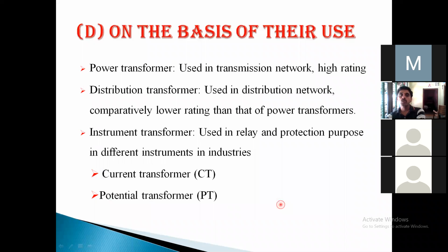So on the basis of use: power transformer, distribution transformer, instrument transformer. They are used in high power network, distribution network. Instrument transformers, actually they are called measurement transformers, CTPT. They are used for measuring the current and voltage, because in the power system lines, there will be high voltage, high current. You cannot measure with ammeter, voltmeter. That's why you will use CTPT. Using that, you will measure the current. If there is 500 amperes, that is converted into 2 amperes. If there are some kilovolts, that is converted into some volts. So like that, we will measure.